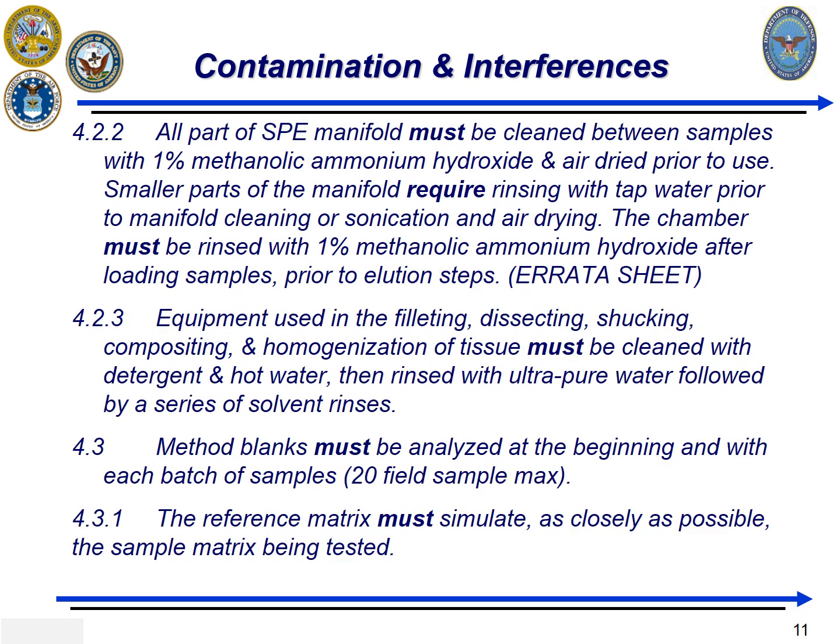The errata sheet the EPA has issued has made changes to section 4.2.2. The corrected text reads, all parts of the solid phase extraction manifold must be cleaned prior to samples with methanolic ammonium hydroxide 1% and air dried prior to use. Sonication with methanolic ammonium hydroxide 1% may be used for components that will fit into an ultrasonic bath.